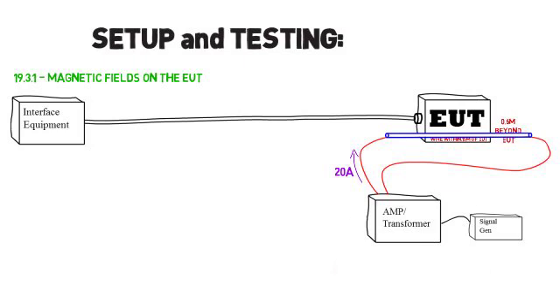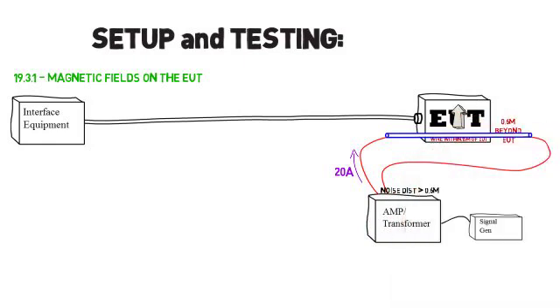The source of the noise must be a minimum of 0.6 meters away. Simply sweep the radiating wire from the front face of the EUT up to the top, then go across the top and down the back edge. Then rotate the straight wire 90 degrees with respect to the EUT and repeat the test on the untested edges.